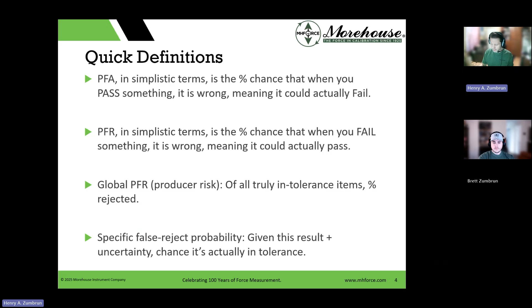So that's PFA, PFR. Now, this gets confusing because there's this term global. That means out of a population, producer risk, which means out of all the truly in-tolerance items, a percent that's rejected. And then specific false reject probability is, given the result plus uncertainty, the chance it's actually in tolerance. We'll go over these in more detail, but most guidance focuses on PFA, false accept, consumer risk. That's the one saying we're shipping a bad product. PFA is saying something's good when it's actually bad, and companies will go to great lengths to make sure that doesn't happen.